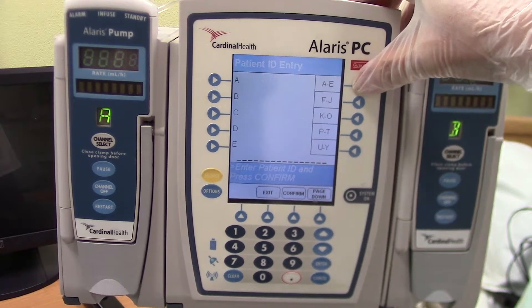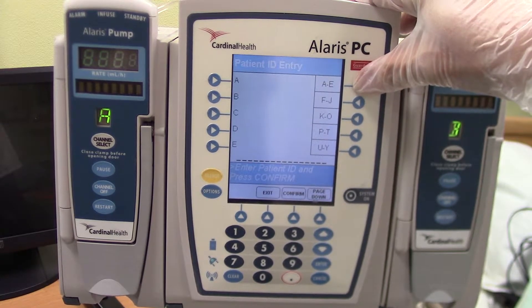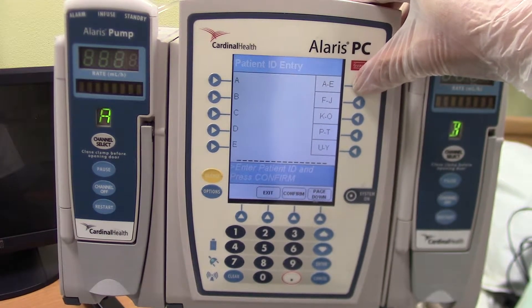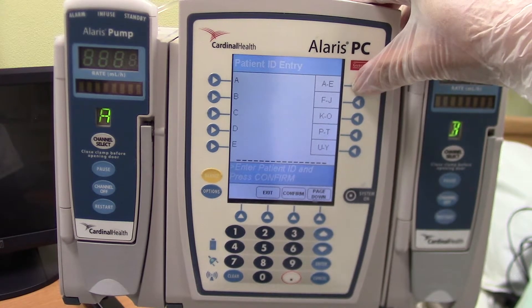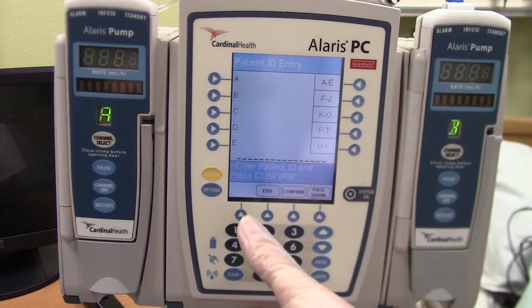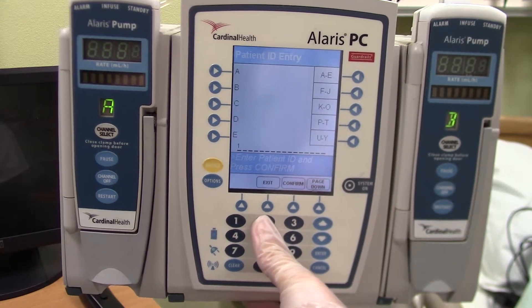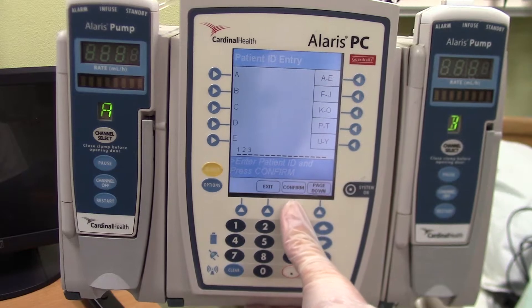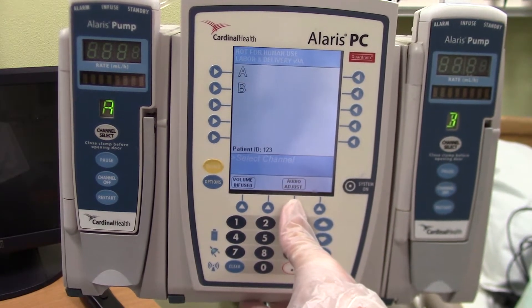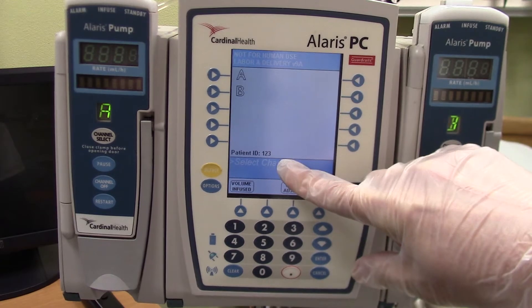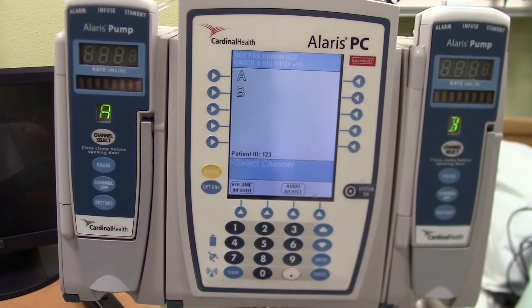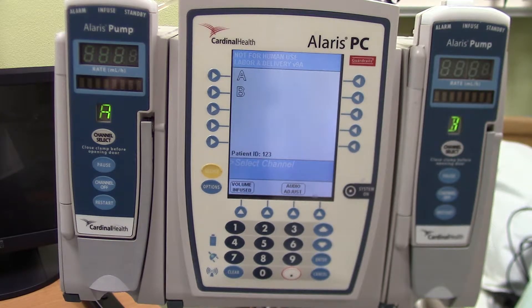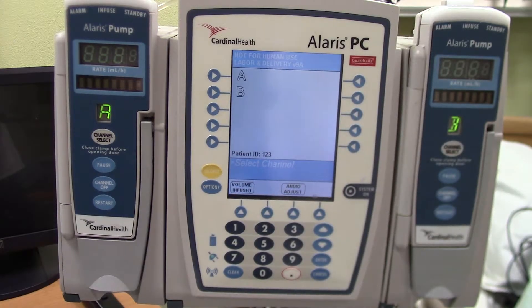It's going to ask me to enter a patient ID. I can use a patient ID with letters or with a number. For this demonstration, I'm going to program the patient ID as 1-2-3. I need to confirm that. And now it's set, showing me a patient ID of 1-2-3. I could obviously use the medical record number, and that would give me an extra set of identification or matching of the pump to the patient.